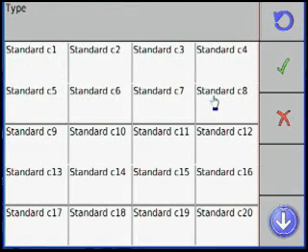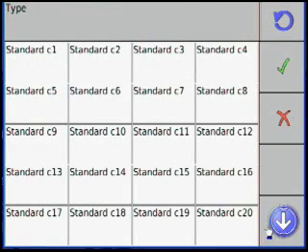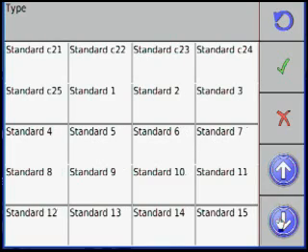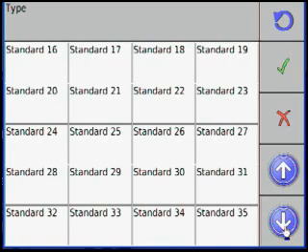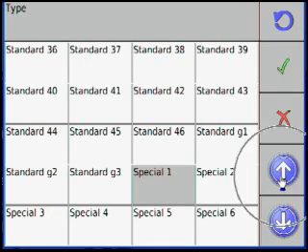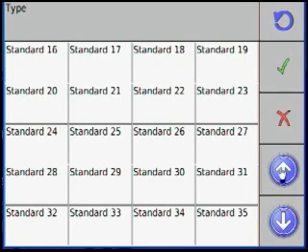When finished, select the check mark. Next, select Type. Incon offers several standard types that have pre-programmed tank charts, but we typically recommend going with a special tank to have the most precise and accurate numbers.